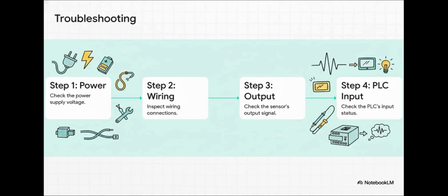For a technician on the floor, it's all about a logical process of elimination. First, check the power supply: is the sensor even turned on? Second, physically inspect the wiring: is anything loose, frayed, or damaged? Third, grab a multimeter and test the sensor's output signal directly: is it actually sending the right message when triggered? And finally, look at the PLC's input status light to confirm if the brain is actually hearing the signal.